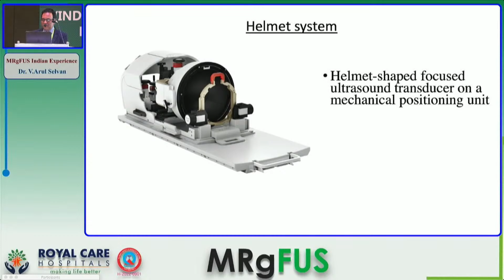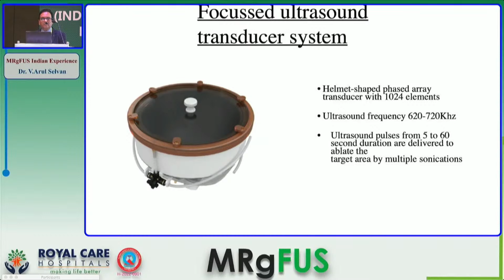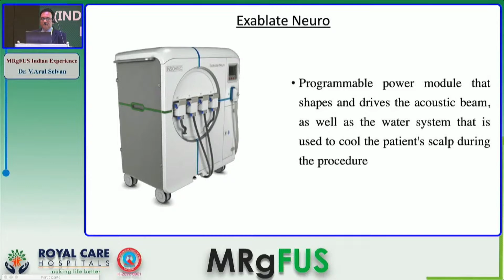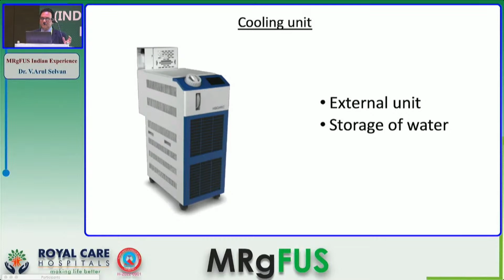The helmet-shaped transducer has 1024 ultrasonic elements. The ultrasound frequency is usually about 620 to 720 kHz. The pulses range from 5 to 60 seconds and are delivered to ablate the target area by multiple sonications. Sonication is nothing but giving high frequency ultrasound energy. This system has a programmable power module that shapes and drives the acoustic beam, and a water system is connected along with it. The water cooler system is outside the MRI unit and sends in the cold water.